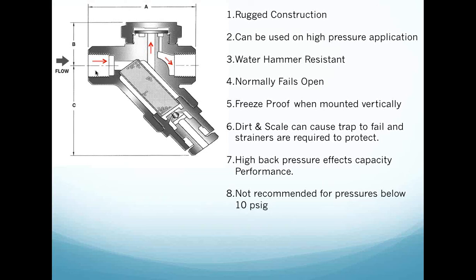So if we have the ability, let's say, to bring 100 psig of steam at 338 degrees, and we have the ability to knock it down and supply 15 or 30 pound steam to a heating application, I want you to know there is way more latent heat of vaporization in that 30 pound steam, 15 pound steam, than there is in that 100 pound steam.